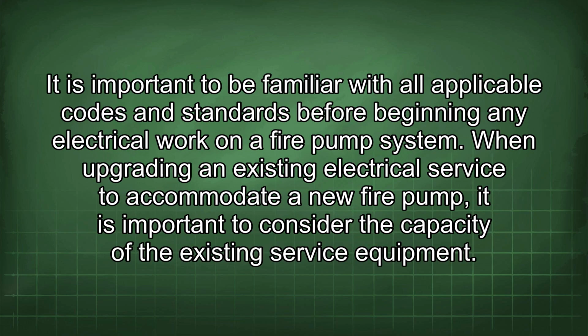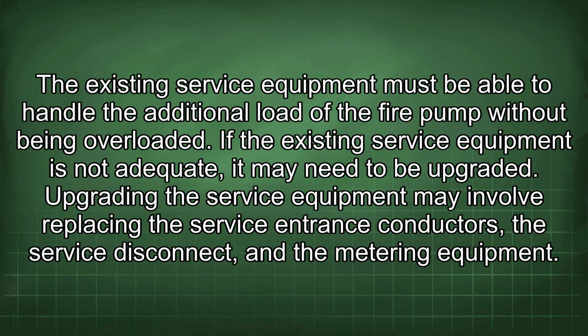It is important to be familiar with all applicable codes and standards before beginning any electrical work on a fire pump system. When upgrading an existing electrical service to accommodate a new fire pump, it is important to consider the capacity of the existing service equipment. The existing service equipment must be able to handle the additional load of the fire pump without being overloaded. If the existing service equipment is not adequate, it may need to be upgraded. Upgrading the service equipment may involve replacing the service entrance conductors, the service disconnect, and the metering equipment.